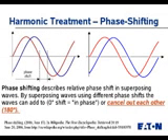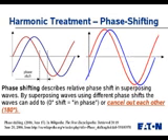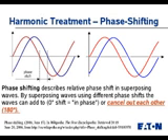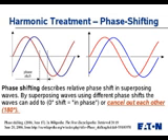The next technique used inside of the HMT is one to mitigate fifth and seventh harmonics in an electrical power system. This is called phase shifting. Phase shifting describes the nature of what occurs when you have two similar waves. When waves are in phase with each other — a zero degree shift — they have a tendency to be additive. When these waves are 180 degrees out of phase with each other, they have a tendency to cancel each other out. We use this technique in the HMT to mitigate fifth and seventh harmonics on a system-wide basis.